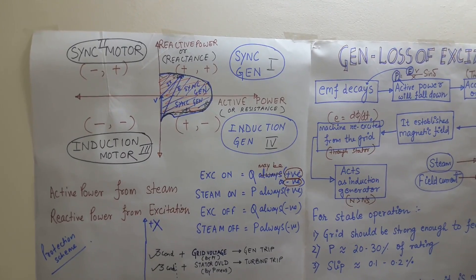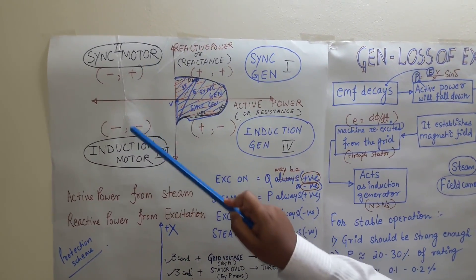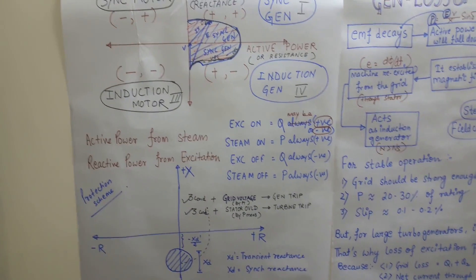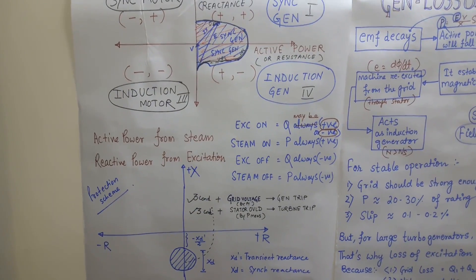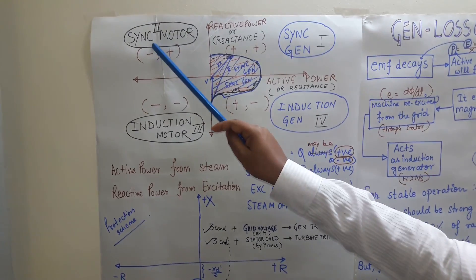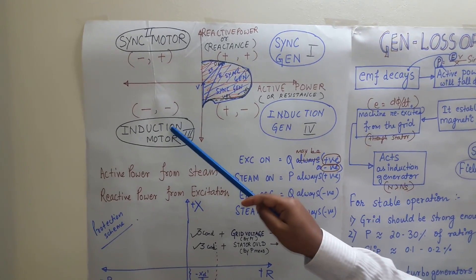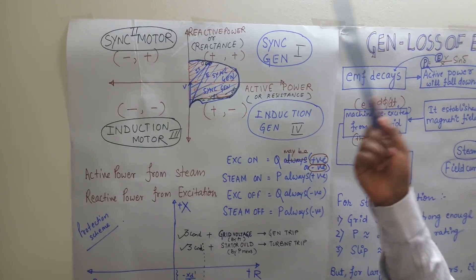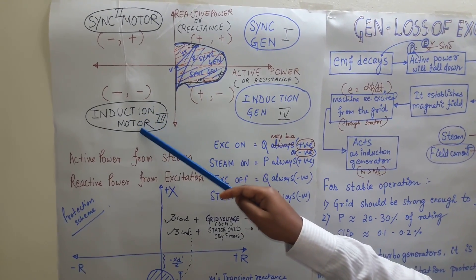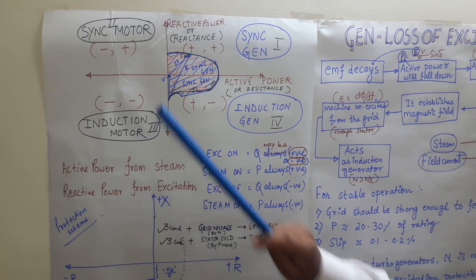During loss of excitation, the generator will operate in this zone as an induction generator. During loss of prime mover, the generator may operate in the second or third quadrant depending upon the excitation. If excitation is strong, it will operate in the synchronous motor zone. If there is no excitation, it will also take excitation from the grid and run as an induction motor with speed lower than the synchronous speed.